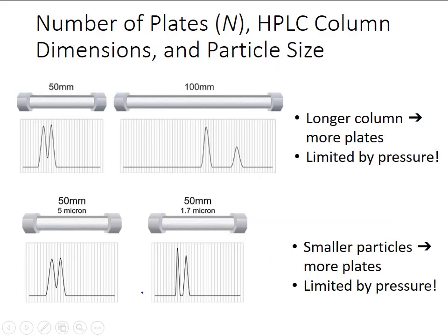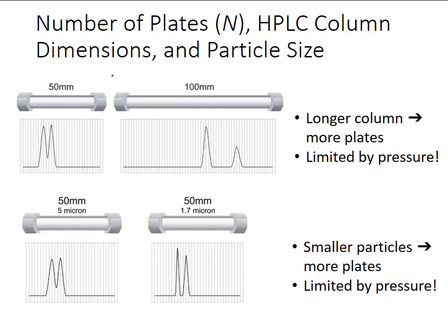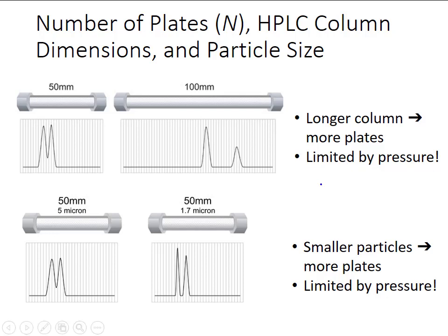In HPLC we can increase the number of theoretical plates by simply making the column longer. We see the resolution of two peaks in a 50 mm column versus a 100 mm column — a longer column leads to more plates and better resolution. But the problem with making a column longer is that we have to push a viscous mobile phase through more stationary phase particles, creating high pressure. The length of an HPLC column is limited by the pressure the instrument can generate; if you exceed that pressure, the plumbing breaks open and mobile phase leaks everywhere.